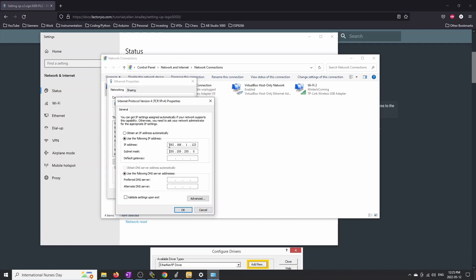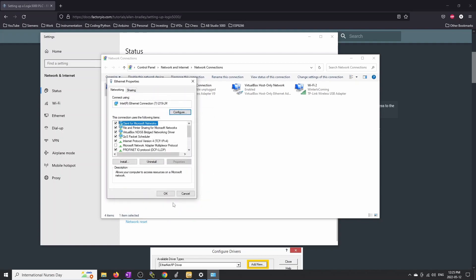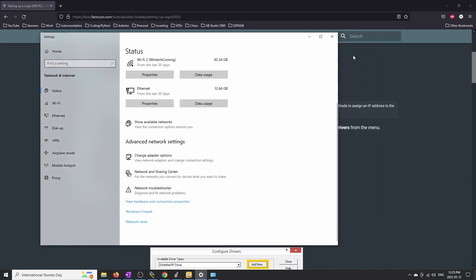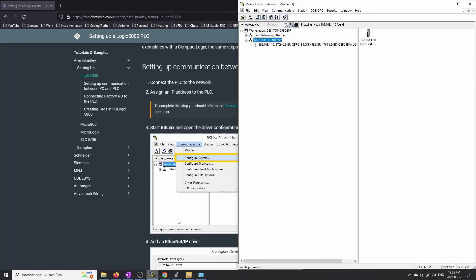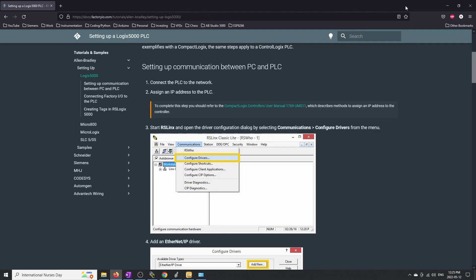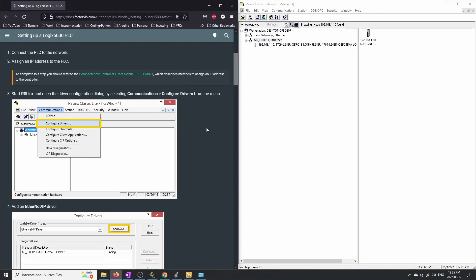So we're using a static IP address for our computer, and the first three numbers — 192.168.1 — will match with the address we use for the PLC. Now let's minimize that and open up RSLinx. The first step is always to open up RSLinx and go to Configure Drivers. I already have an Ethernet connection up and running that connects to my PLC at 192.168.1.10. You can see those first three sets of numbers are identical to what we just set for the Ethernet connection on the computer.